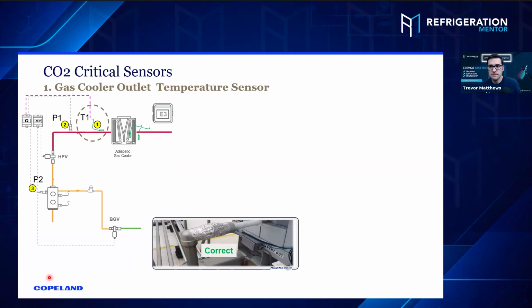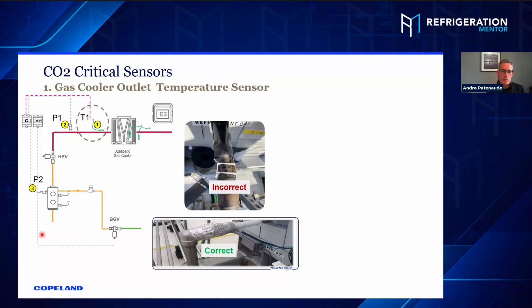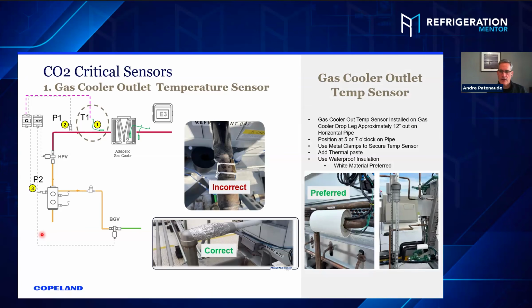Because that sensor is so important, it's important that it's properly insulated at the gas cooler outlet, like I'm showing here. Don't do that. Don't tie it with tie wraps on an open pipe with the sun beating on it uninsulated. That is not a good situation, because you're not going to get the right temperature. The recommendation is gas cooler out, close to it, at least 12 inches or shorter to the outlet, 5 or 7 o'clock.